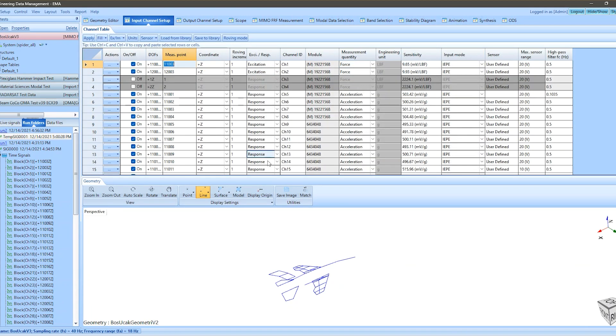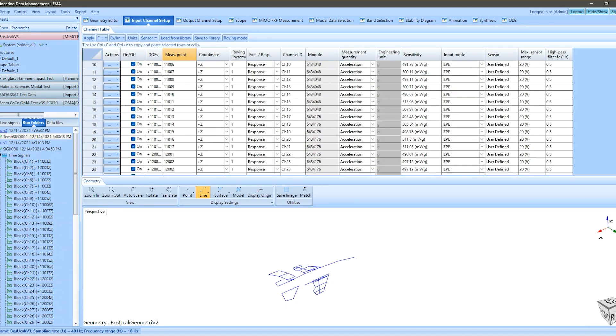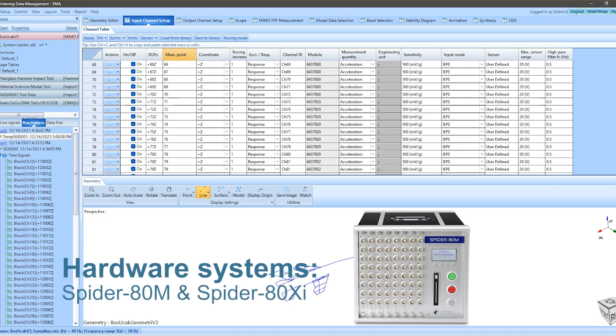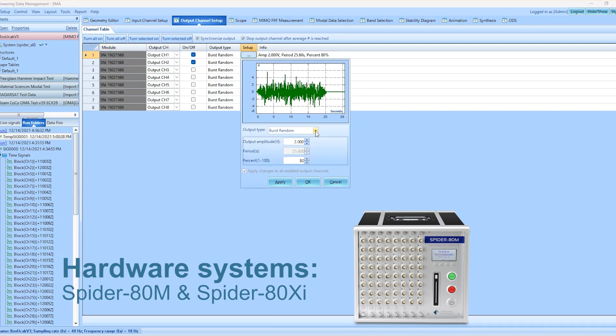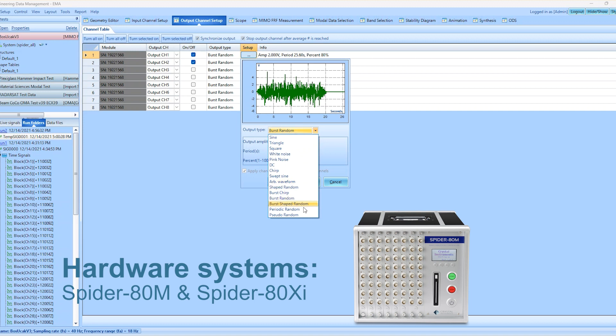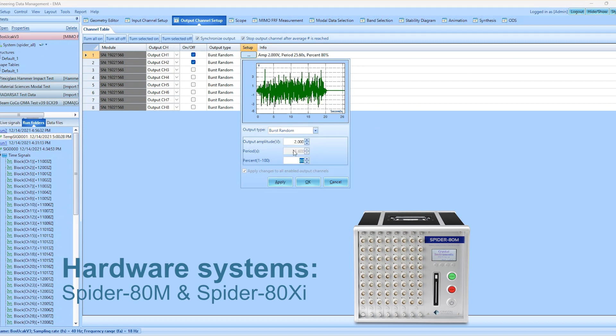Hardware systems like the Spider-80M and Spider-80Xi, equipped with chassis structures featuring interchangeable slots, prove highly useful for GVT. Additionally, accurate time synchronization ensures excellent phase matching between channels. With patented dual ADC technology, these systems can detect signals as minute as 6 microvolts and as large as 20 volts on each measurement channel.